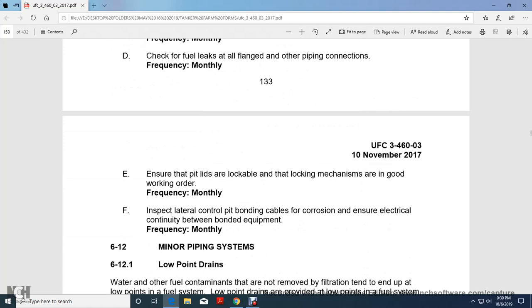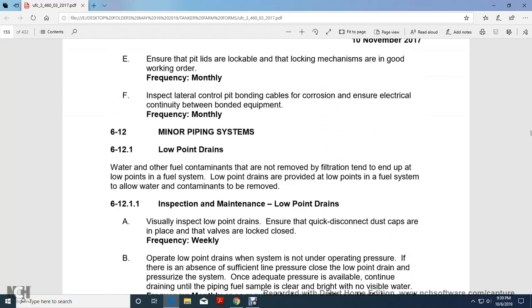Ensure pipe pit lids are lockable and locking mechanisms are in good working order, monthly. Inspect lateral control pit bonding cables for corrosion. Ensure the electrical continuity between bonded equipment, monthly.